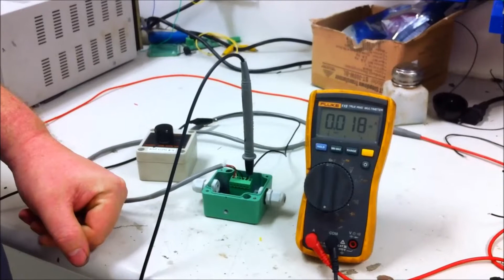So what we'll do now is I'll get a screwdriver in there, and I'll start turning that little multi-turn pot clockwise until I get more than 16 milliamps from memory. You probably don't want to go to 20, because then it won't be able to register an overload. But if I take it up to about there, that receiver should be able to do a calibration now.